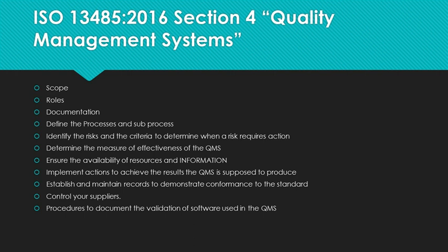You need to define roles. They must be documented and identify the applicable regulatory responsibilities and authorities for each role. If the FDA must be notified, who is doing what tasks? Who collects, documents, and reviews complaints for reportability? Having an employee unclear about who they are reporting to or what they are reporting is not an acceptable reason for missing reporting an incident.